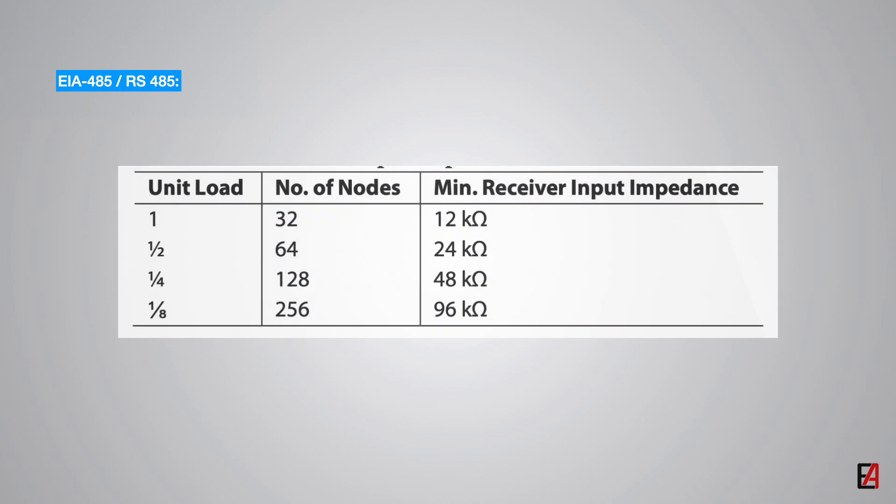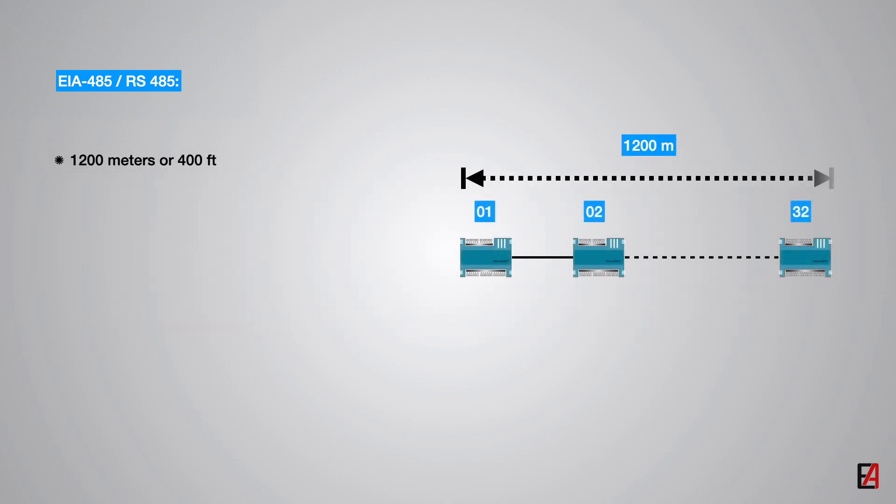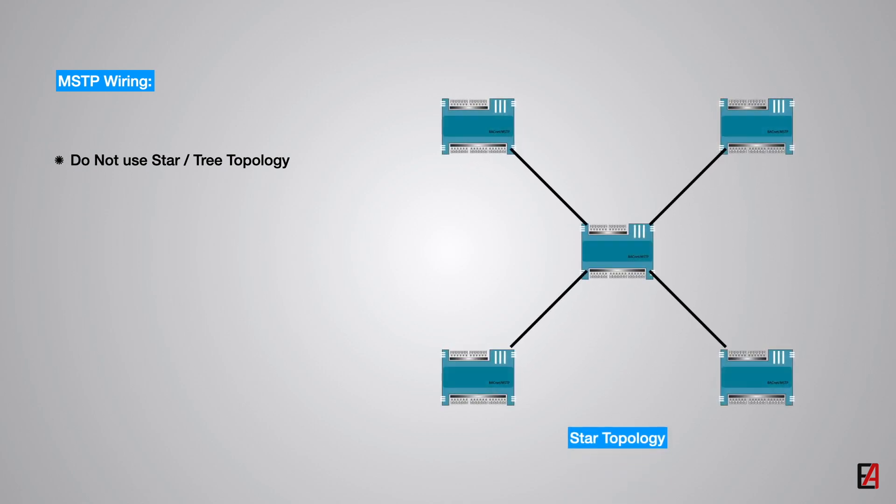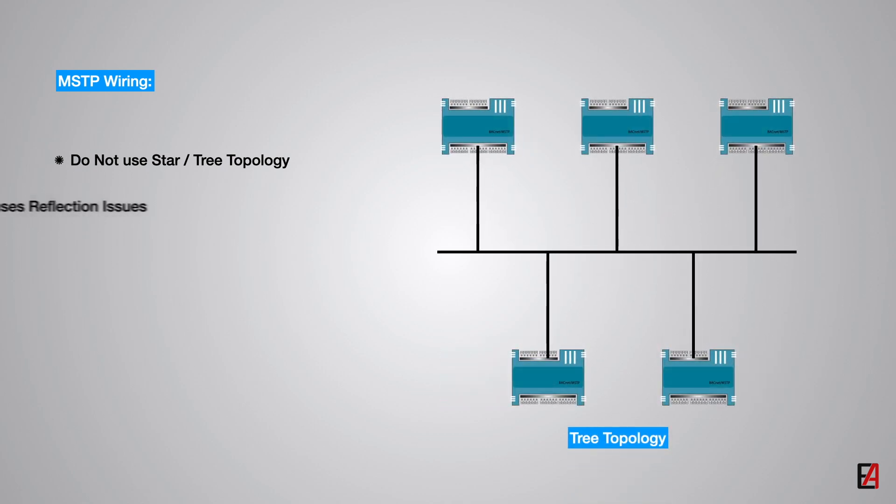The table here summarizes the RS-485 standards requirement. The RS-485 standard defines the maximum physical length of an MSTP network as 1200 meters or 4000 feet. The communication wiring of MSTP is very important. MSTP does not support star or tree topology as using these topologies causes pulse reflection issues on the network.